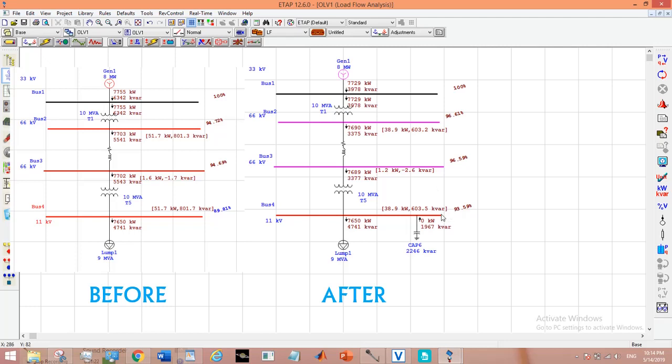And also the bus voltage has been improved. Before capacitor it was 89% and now it has improved to 93.5%.